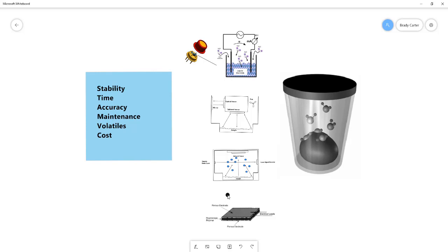Now, when we talk about accuracy, of course, we're talking about whether or not the right value is measured, versus precision, which means do you get the same answer every time? And really, this can only be measured on specific samples because you have to know the water activity. So there are both saturated salt solutions and unsaturated salt solutions available for doing these measurements. And the accuracy and precision that's reported is always measured on these types of samples under ideal conditions.